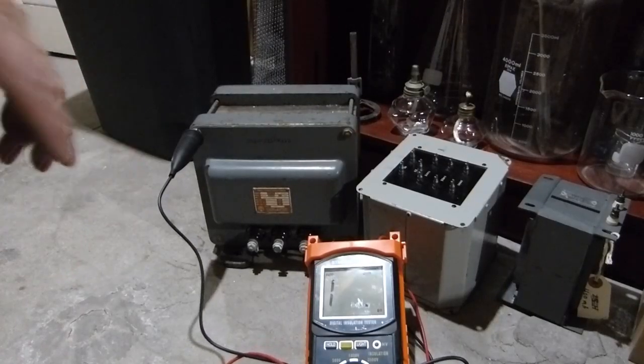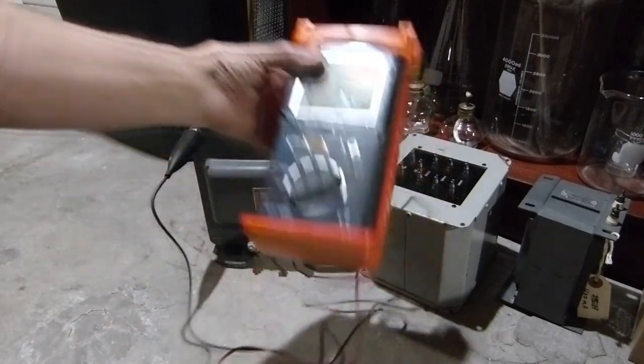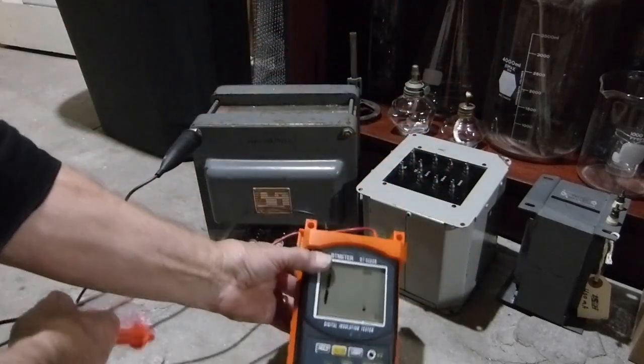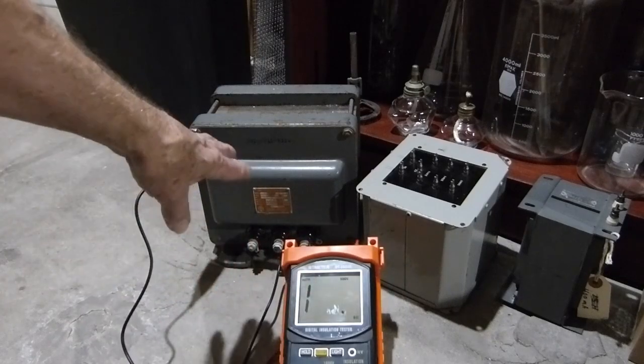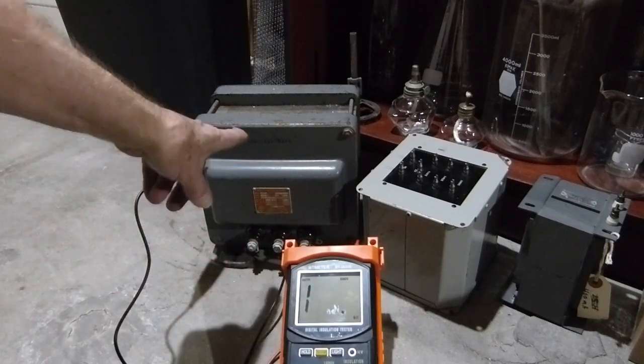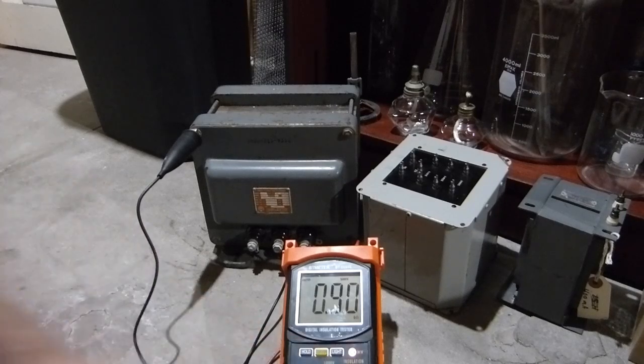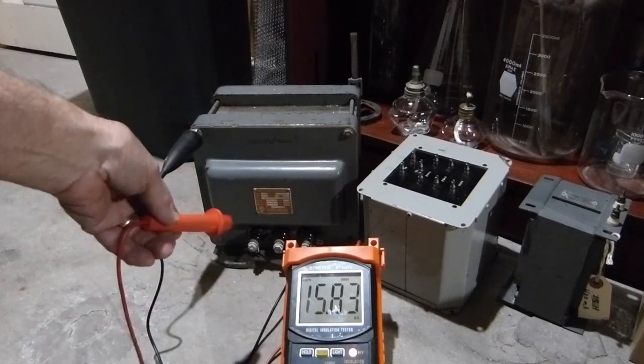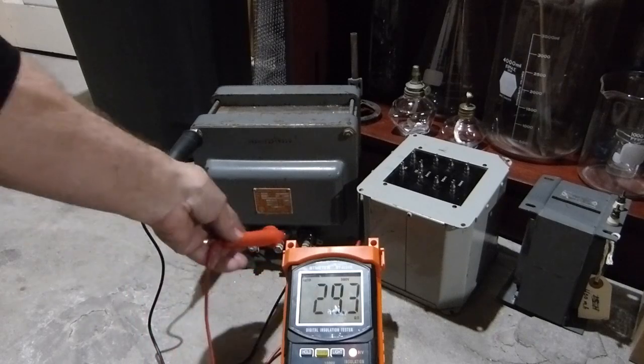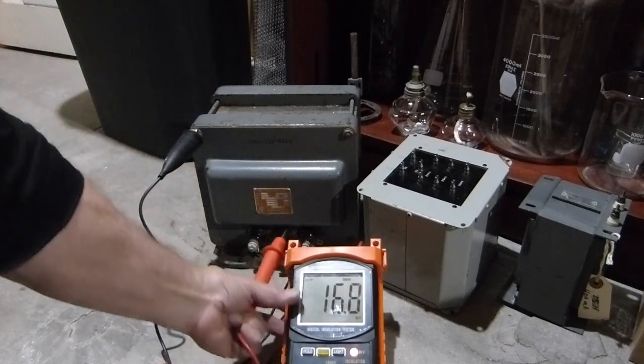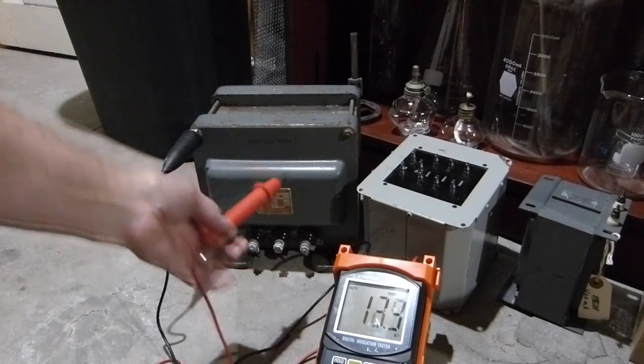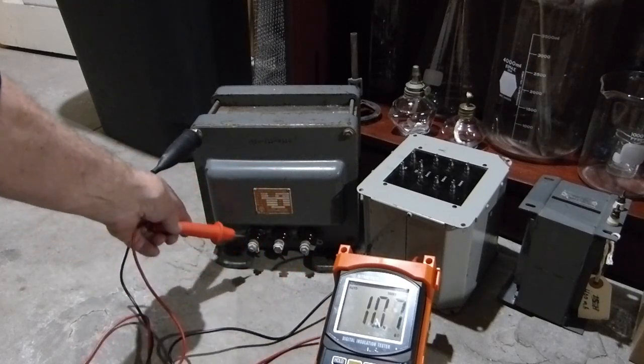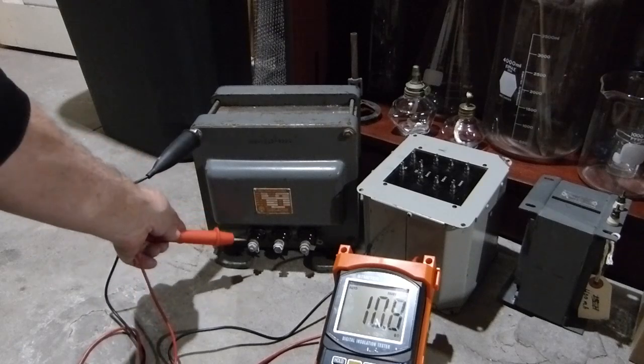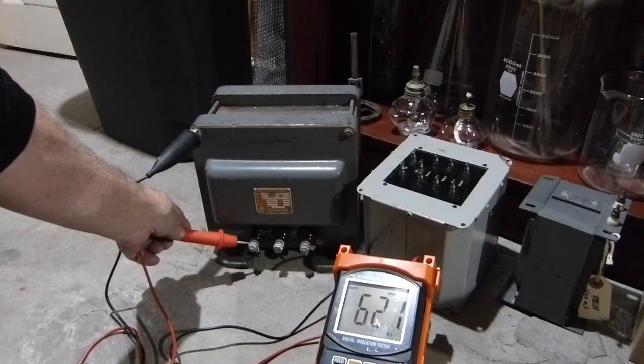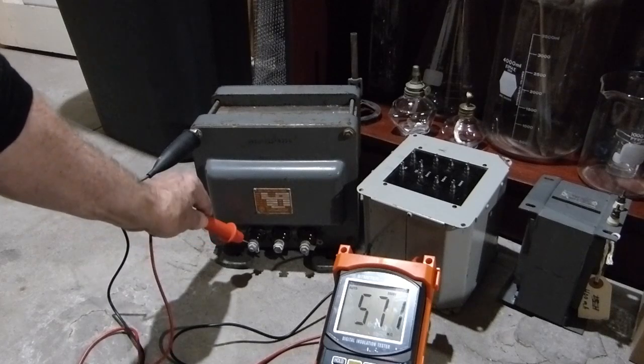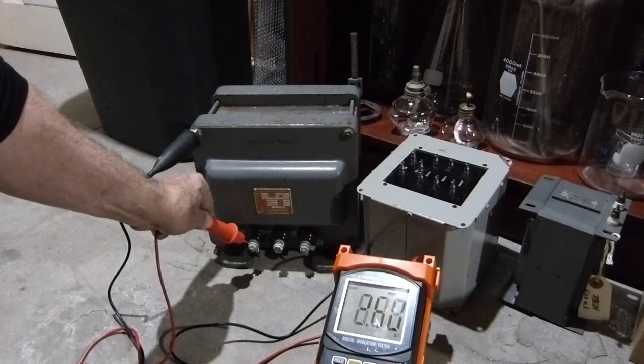Here's an actual intended use for one of these meggers. This is a 3700 volt transformer, weighs 62 pounds. I'm turning this on to test the insulation of the high voltage terminals down here to the case. You can actually see it. I think you'll be able to see a little tiny arc even... yeah, see there? See a little arc? And it says it sits up in the gig ohms.